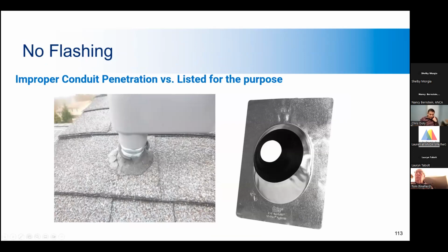The left-hand picture is an improperly sealed roof penetration. The contractor drilled through the roof, and then rather than sealing it properly, used duct seals, which is not an appropriate way to seal the opening. It doesn't look great, and it's basically putty that goes around the hole. And it's somewhat weatherproof, but it's not being used correctly here. And on the right, we see the correct piece of equipment that should be used for this penetration. There are two applicable codes, the New York State Residential Code and the New York State Building Code. And depending on the occupancy, if it's residential or non-residential, specific information on flashings can be found in the roofing section of the checklist.